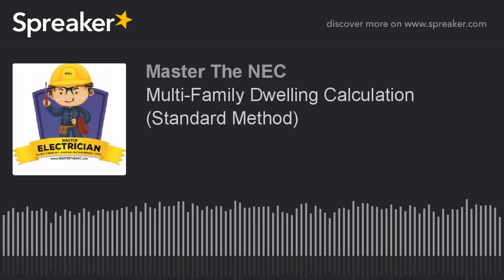And it is single phase. So we're going to 430.248. Single phase, and at 230 volts, a 3 horsepower unit is 17 amperes. That's what the load is, 17 amps.